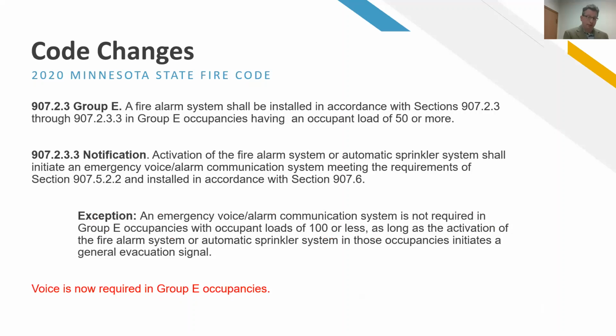Group E occupancies, that's educational, K through 12. This is a pretty simple section: now voice is required in schools. You can't just have a horn for occupant notification, you have to have a pre-recorded emergency voice message. A lot of schools have been doing this voluntarily for the last 10 years or so, but now it's required in the code, and Minnesota is catching up to the way the rest of the country does it, since outside of Minnesota many states have already been doing this. Pretty self-explanatory.